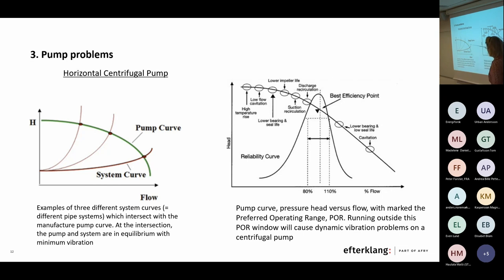That's why it's so important that the system curve should always be updated to what is acting out there, together with the supplier's pump curve. This pump curve may also be updated because the pump wears, so the pump curve will go down here.